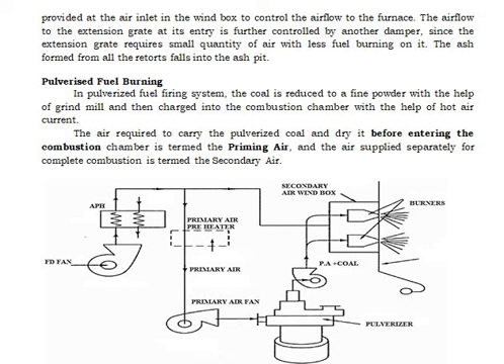In a pulverized fuel firing system, the coal is reduced to a fine powder with the help of a grind mill and then charged into the combustion chamber with the help of hot air current. The air required to carry the pulverized coal and dry it before entering the combustion chamber is termed the primary air, and the air supplied separately for complete combustion is termed the secondary air.